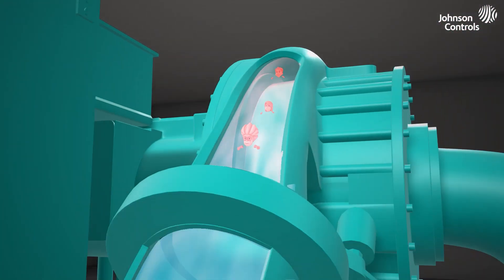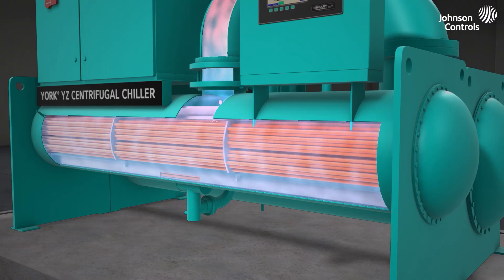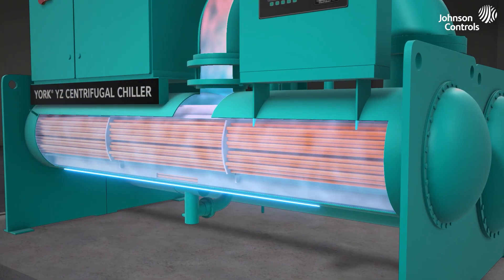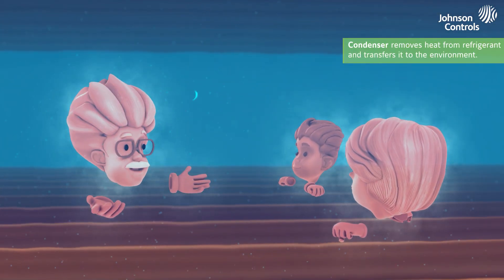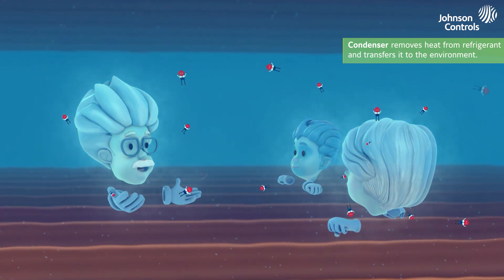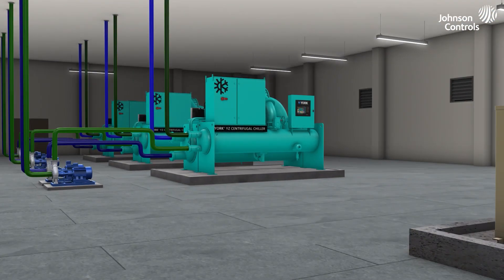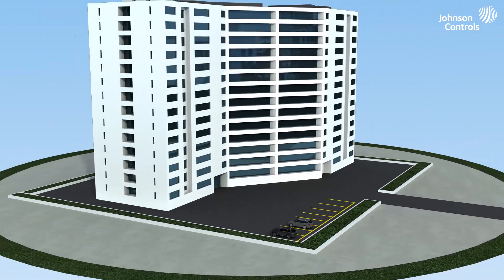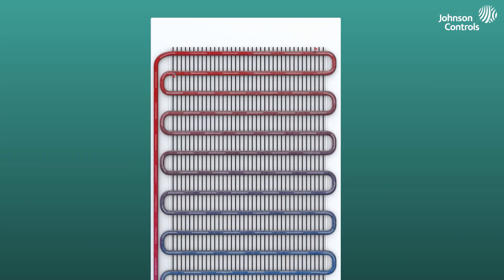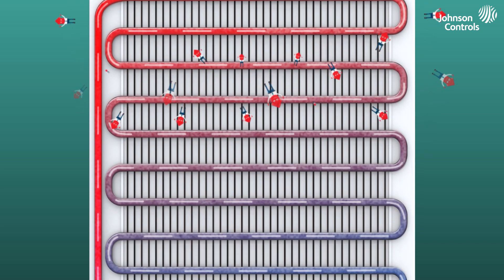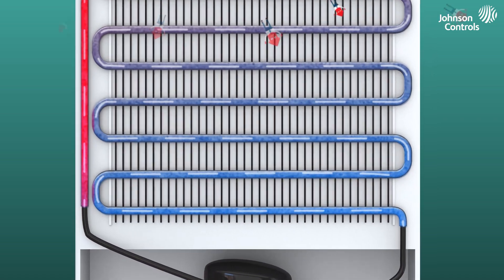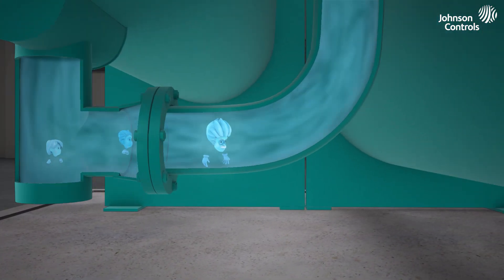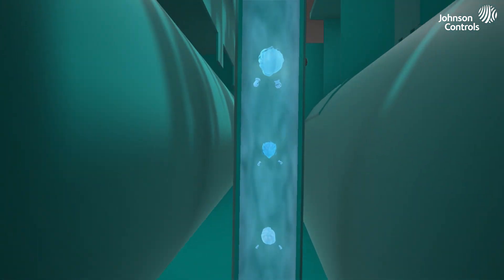The condenser looks a lot like the evaporator, and it performs a similar function, except this time the goal is to remove the heat instead of to absorb it. The condenser is usually located in the place where we want the excess heat to go, whether this is outside of a building or on the outside of a refrigerator. As we move through the coil, the environment will absorb the heat back from us because it's cooler than we are. We're liquid again, but we can't go back to the evaporator until we're low-pressure.